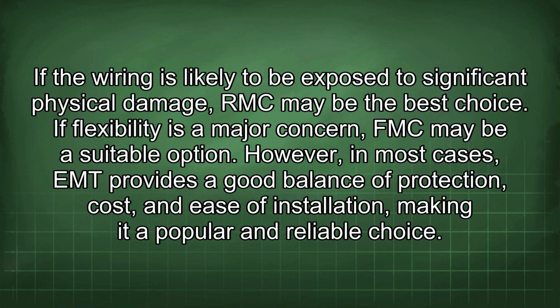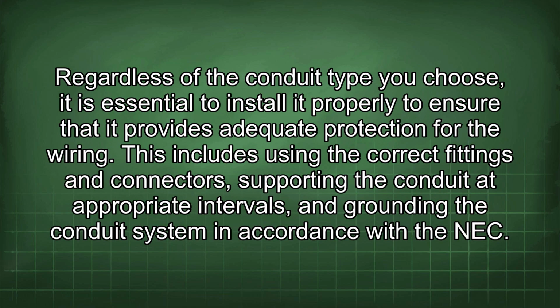When choosing a conduit type for your jacuzzi feeder, it is important to consider the specific conditions in your basement. If the wiring is likely to be exposed to significant physical damage, RMC may be the best choice. If flexibility is a major concern, FMC may be a suitable option. However, in most cases, EMT provides a good balance of protection, cost, and ease of installation, making it a popular and reliable choice. Regardless of the conduit type you choose, it is essential to install it properly to ensure that it provides adequate protection for the wiring.